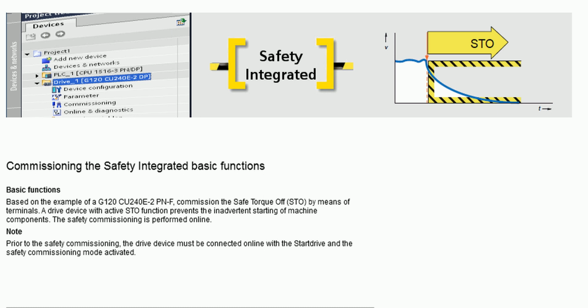Basic functions, based on the example of a G120 CU240E-2 PN-F, commissioned the Safe Torque Off, STO, by means of terminals. A drive device with active STO function prevents the inadvertent starting of machine components. The safety commissioning is performed online. Note: prior to the safety commissioning, the drive device must be connected online with Startdrive and the safety commissioning mode activated.